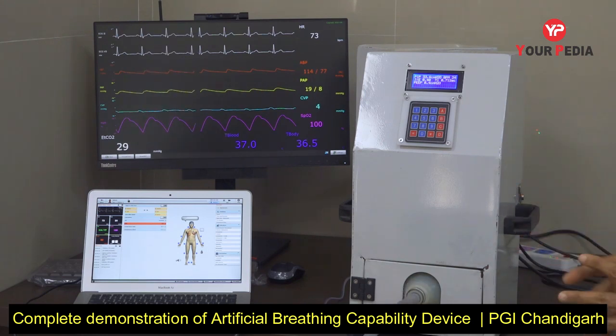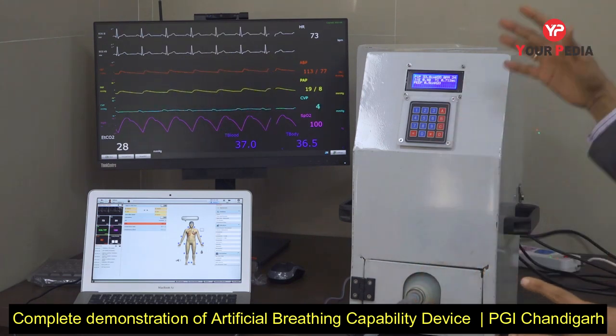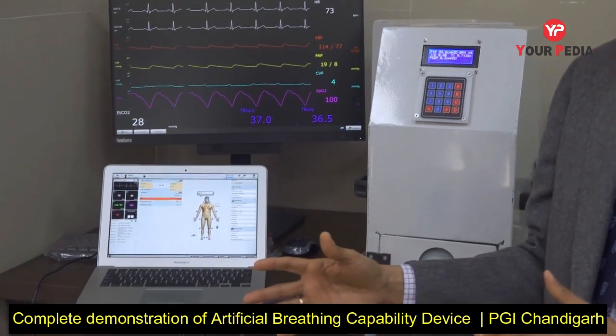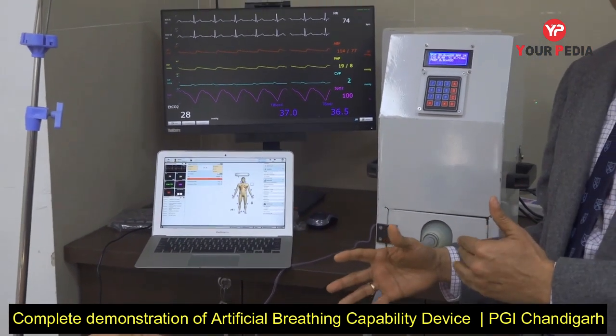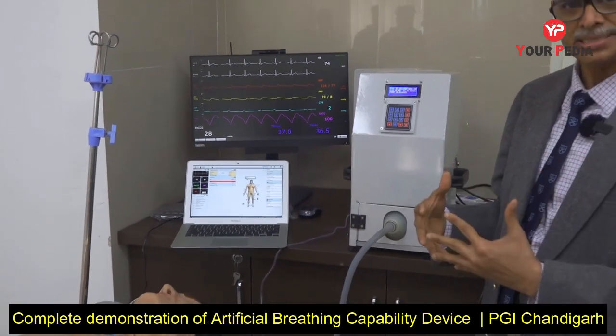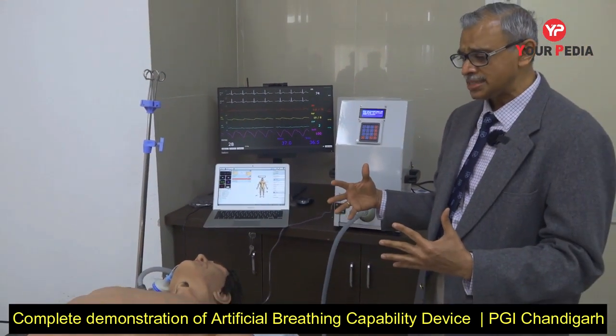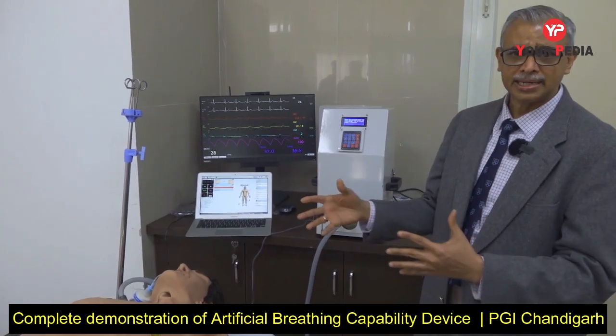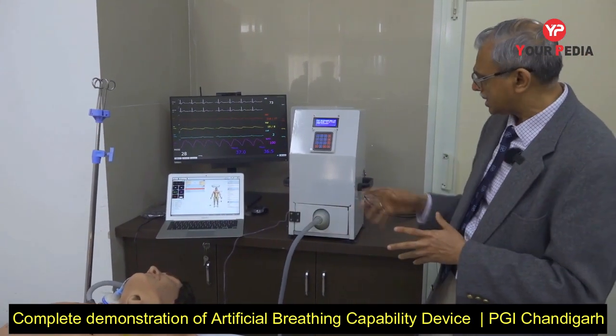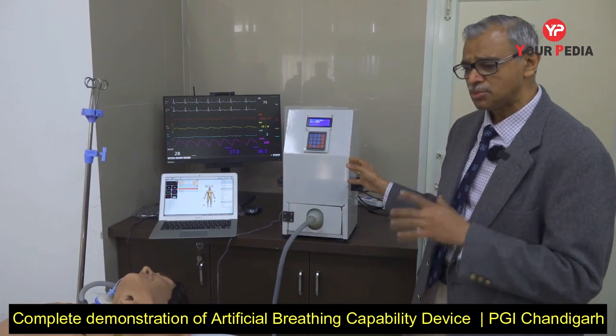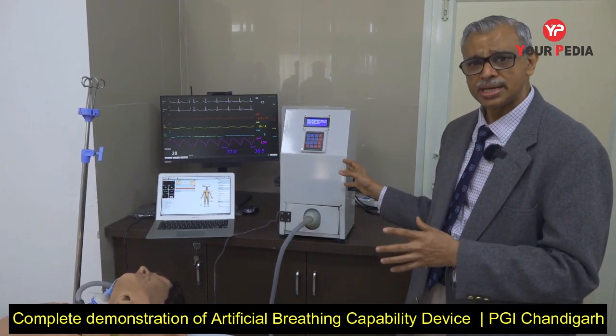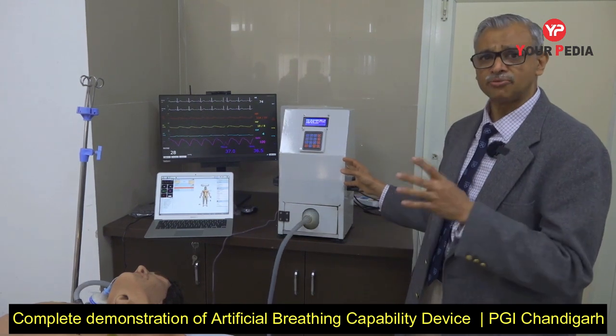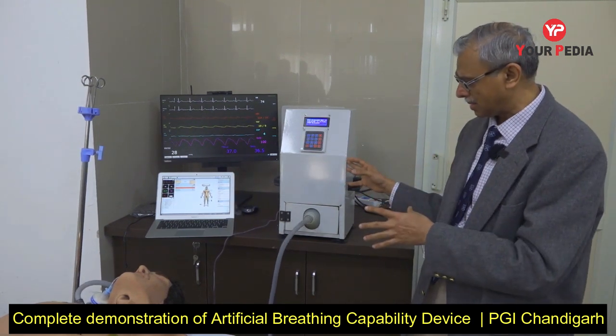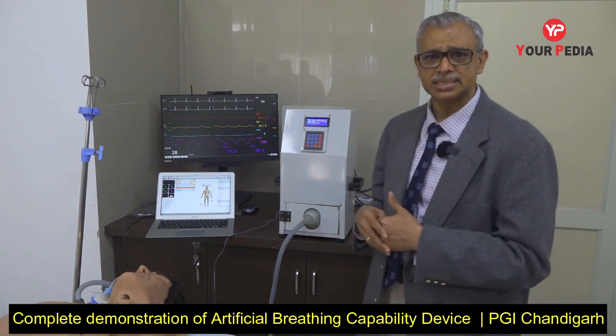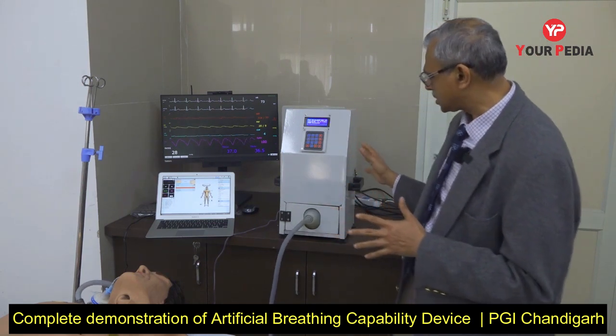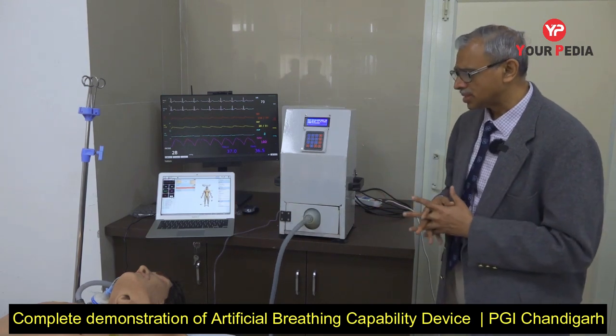And the best feature of course is the cough alert. We know that when the ventilator is trying to push air into the patient's lungs, if the patient is coughing out, the two opposing pressures can work against each other. There is no way for the pressure to be released. It blows back to the lung and can damage the lungs, creating pneumothorax. So this machine is able to actually simulate or recognize that cough and then detect it, pause for 3 to 5 seconds as set by the user, and then resume the settings wherever it was left. So this in a nutshell is how this works in a real world scenario.